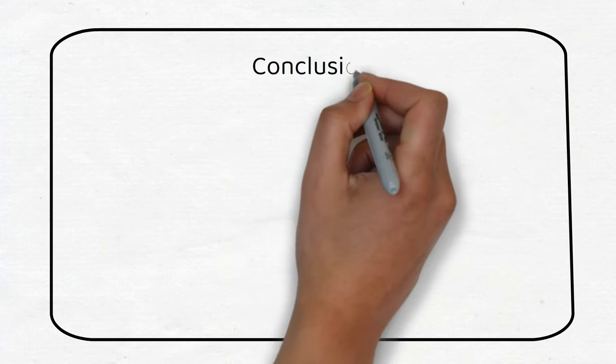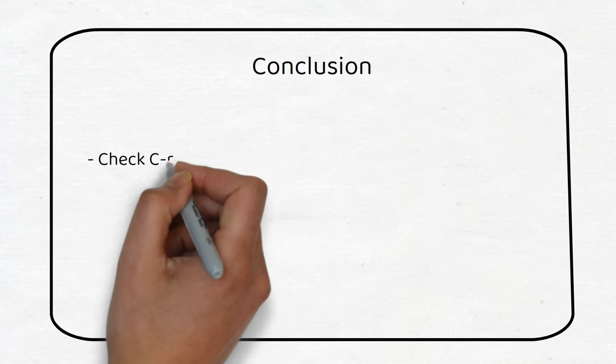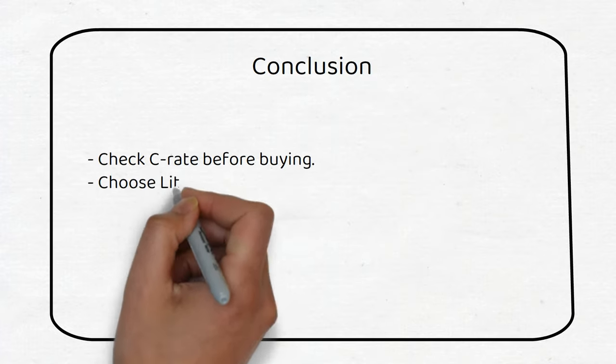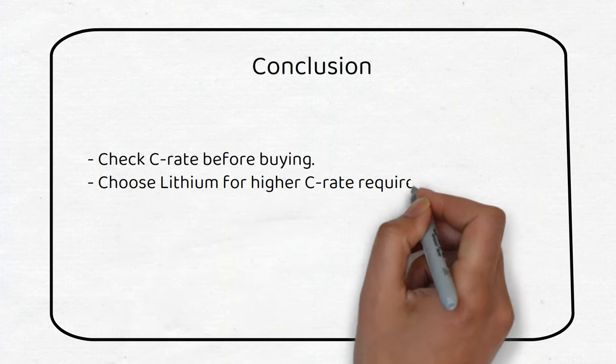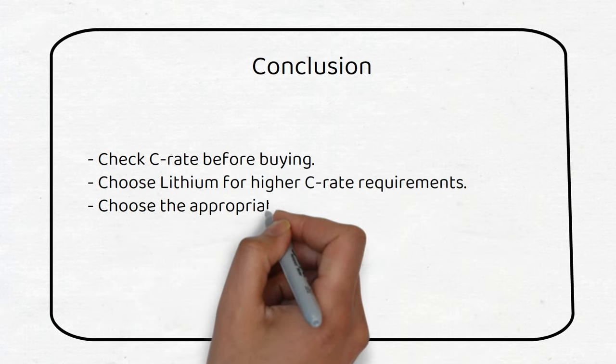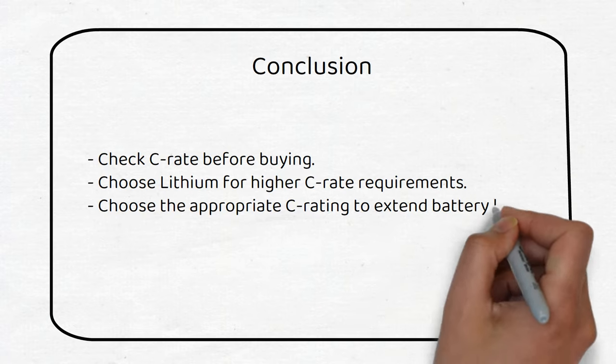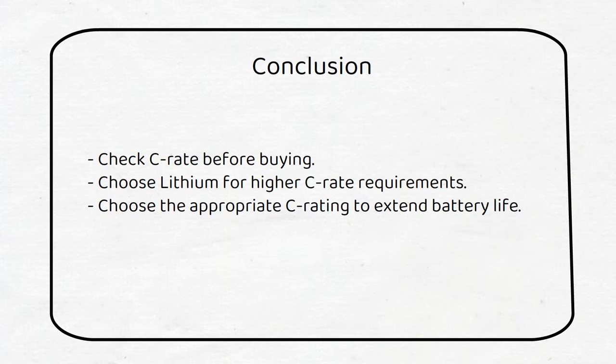Make sure you check the charge and discharge C-Rate of your batteries before buying them. Lithium has higher C-Rates than lead acid. Lithium batteries have a built-in battery management system to shut down the battery if high currents are being drawn. A lithium battery is capable of providing a surge current of 2C for a few seconds, depending on the chemistry.